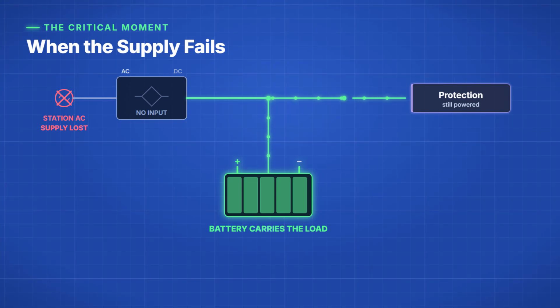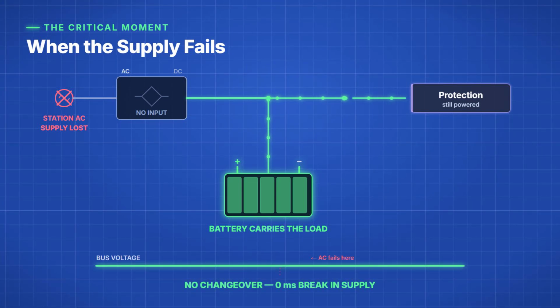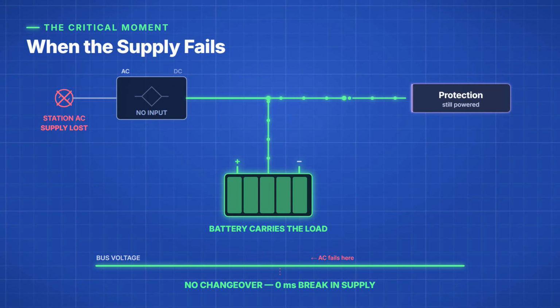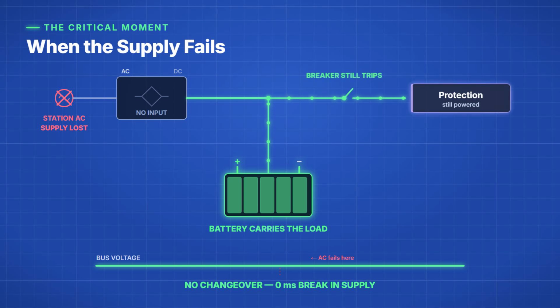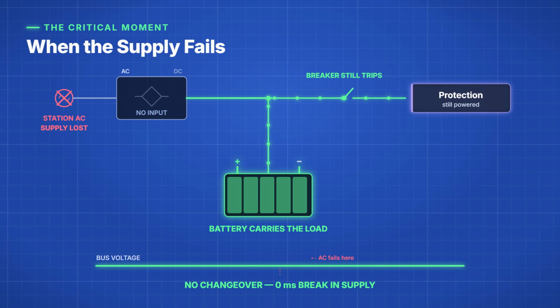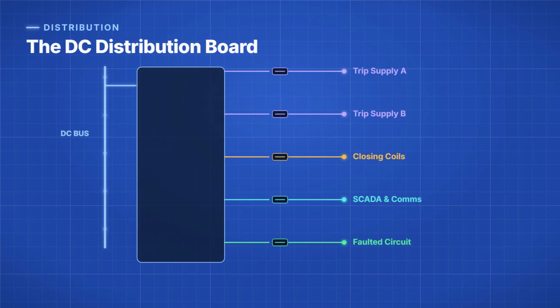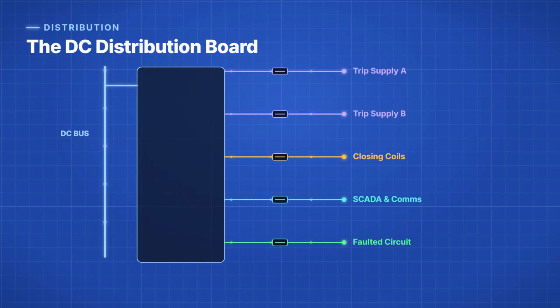There's no switch to throw and no gap in supply because nothing actually had to change over. The relays stay powered, and if a breaker needs a trip, the coil still gets the energy to do it. That seamless handover is the entire reason the battery bank exists. From the DC bus, the power has to be split up and sent to all those circuits safely, and that's the job of the DC distribution board.